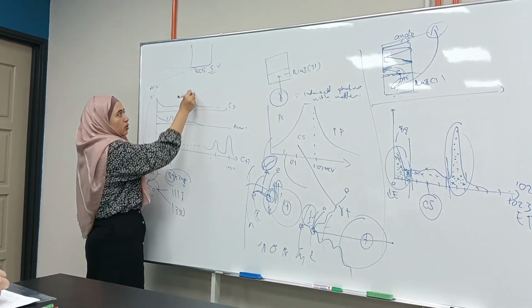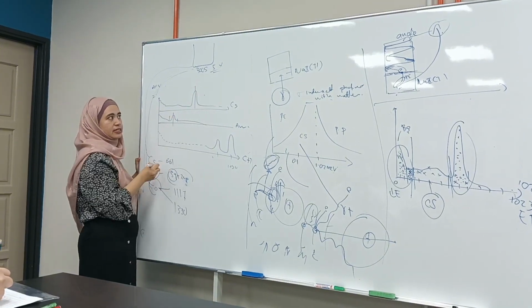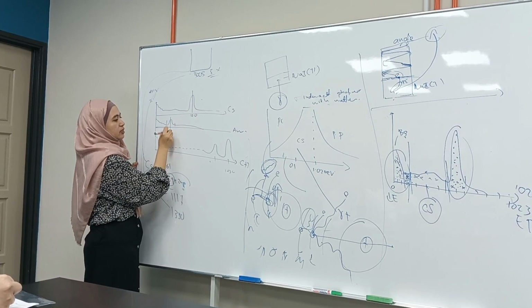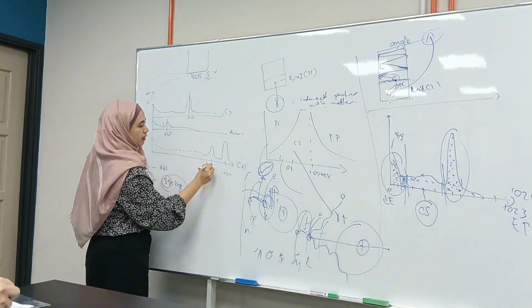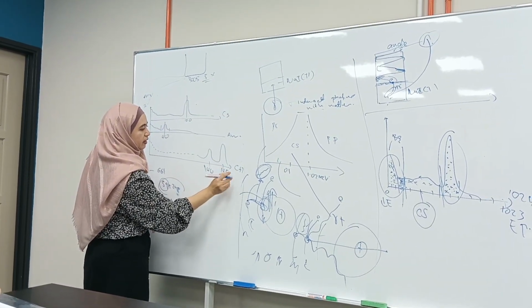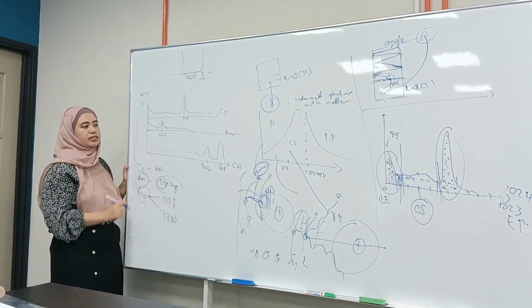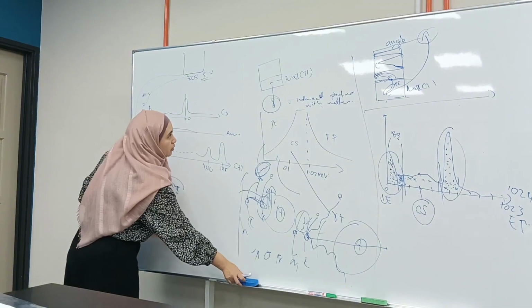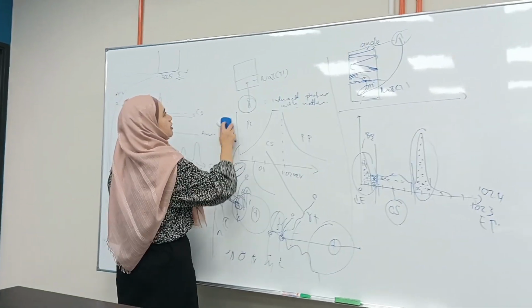So if you go to the system and identify this channel number, let's say this is 100, this is 40, this is 140 and 145. Let's say you have identified all the channel numbers, you can plot the calibration curve. So how do you plot the calibration curve?